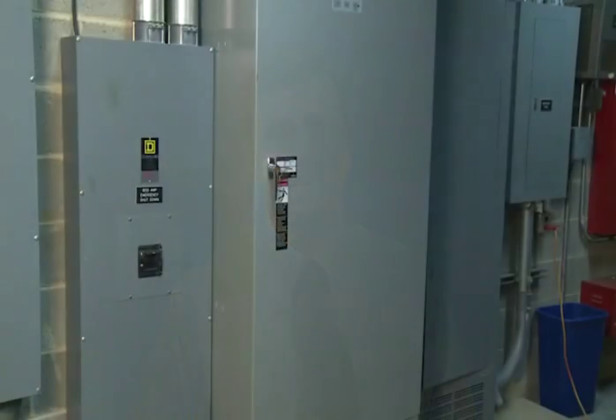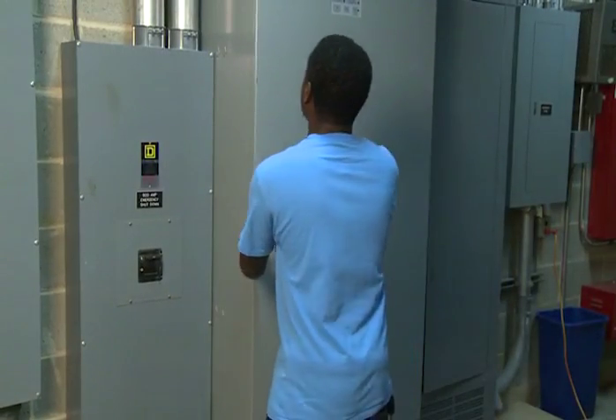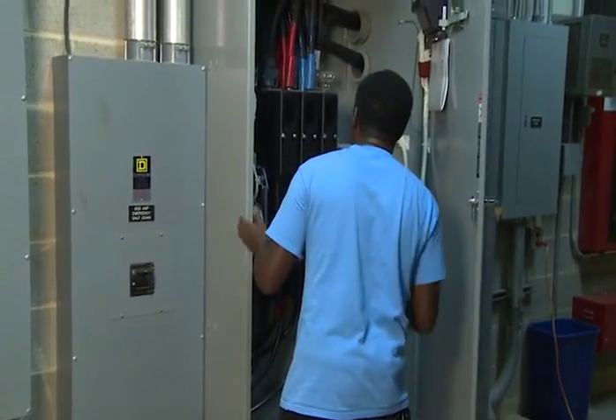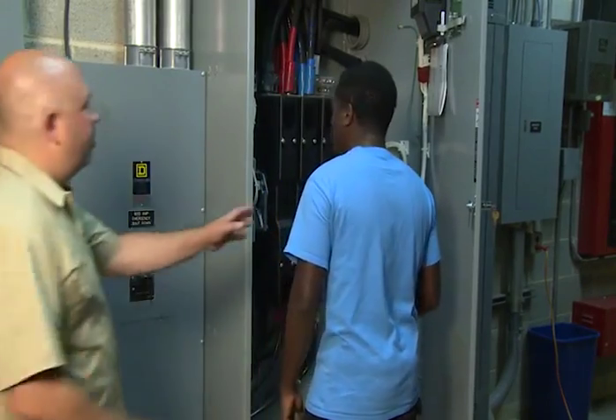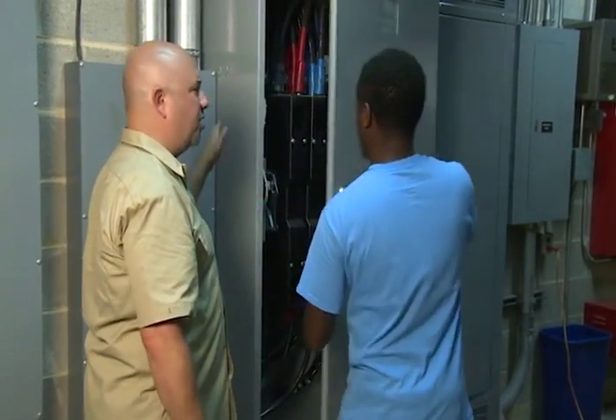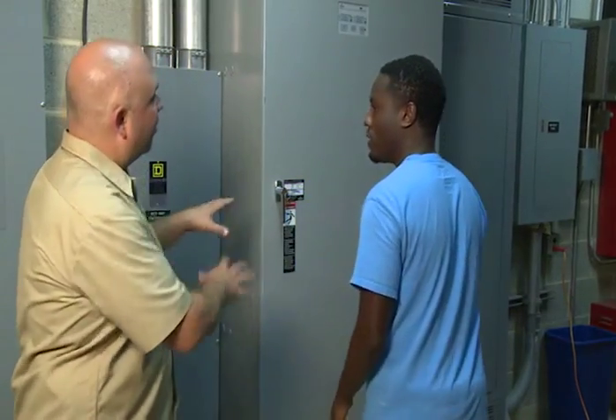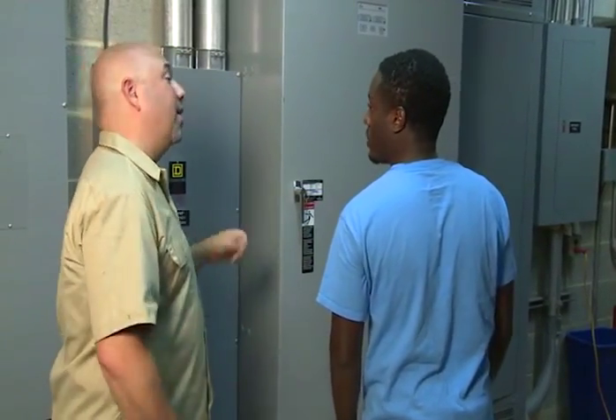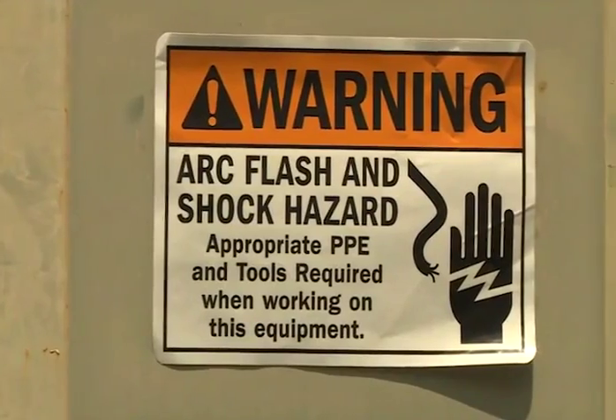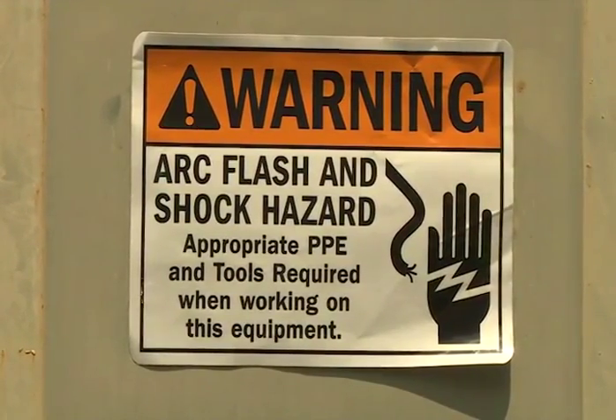While preventing arc flash in your facility largely depends on the safe work practices of the qualified electrical workers who are servicing the equipment, there are things that other employees can do to keep safe around potential arc flash situations as well. First, if you're not qualified and authorized to operate or work on electrical equipment, you shouldn't try. Small mistakes with high voltage can have big consequences. That's why it's also a good habit to stay clear of electrical equipment and potential arc flash sources under any circumstances. Warning labels make arc flash sources easy to recognize so you can keep your distance.